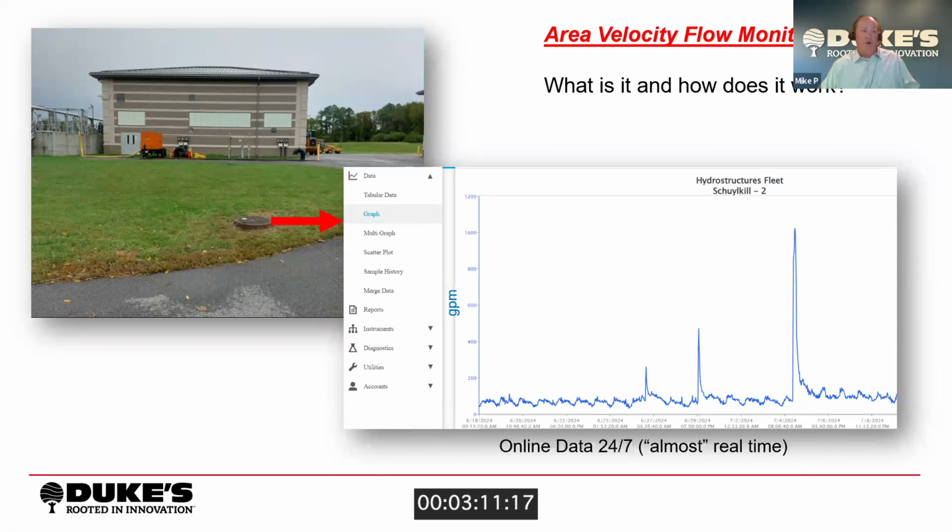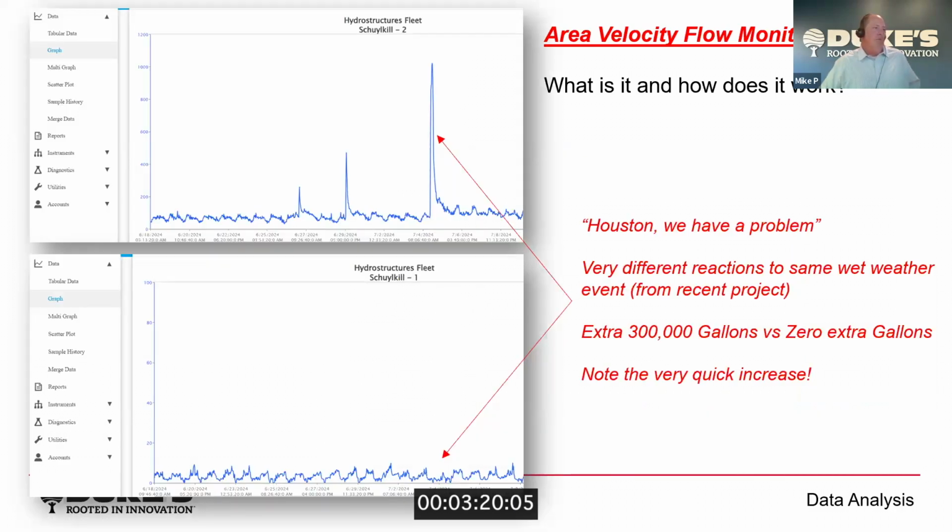If you take a quick hard glance at this graph here, you can see 3 spikes, and those spikes are what I&I looks like on a flow meter. These 2 graphs: the one on the top is the same one, and the one on the bottom is from the same study, only maybe 500 or 700 feet away, but on a different sewer line. The flow meter with the data on the top shows a huge reaction, right? And on the bottom, there's absolutely no reaction whatsoever.